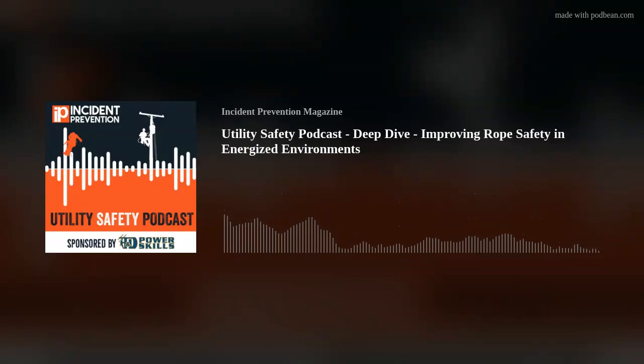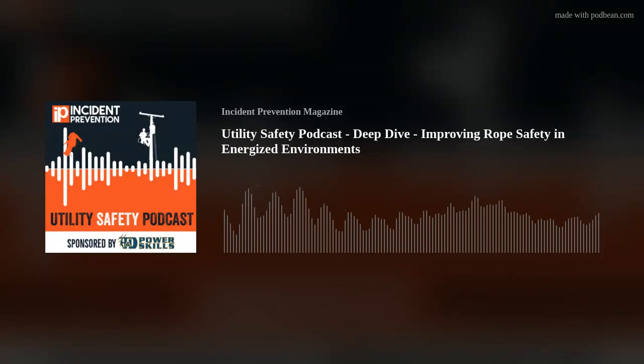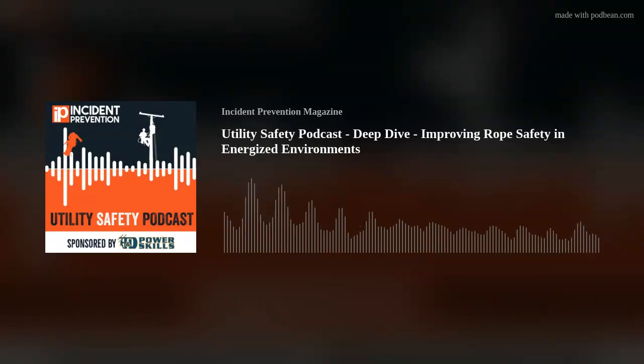Pillar two: second, store and maintain them like other insulating tools. This is critical, they aren't just any old rope you toss in the back of the truck. After use, they need to be cleaned if necessary and stored properly, in a clean, dry, well-ventilated space, away from contaminants, oil, grease, chemicals, even excessive dirt. Inspect them regularly, clean them, and get them periodically retested dielectrically. When transporting, use sealed containers or protective bags. Treat them like the precision safety instruments they are.